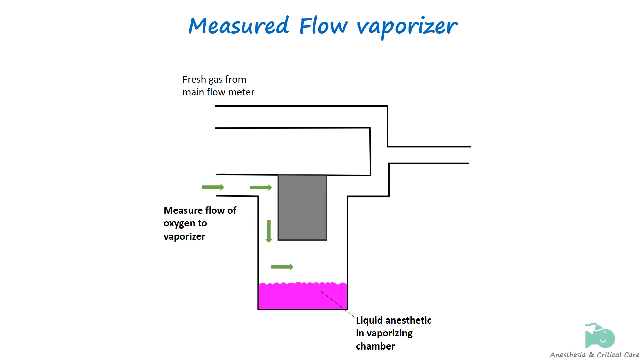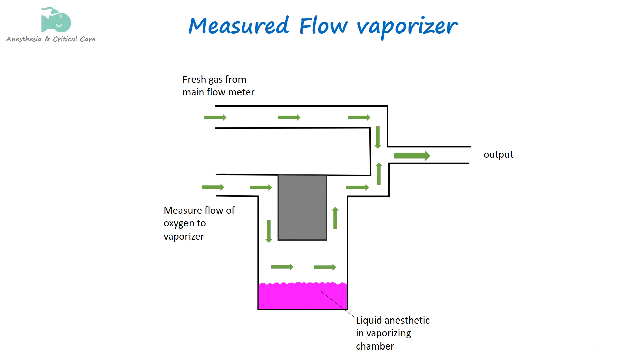In order to dilute this lethal concentration of anesthetic coming out of the measured flow, it is combined with the gases passing from the main flowmeter. So the operator has to set the flow to the vaporizer and bypass with separate flowmeters. This means that respective flows have to be calculated for each agent for a given temperature and vapor output.